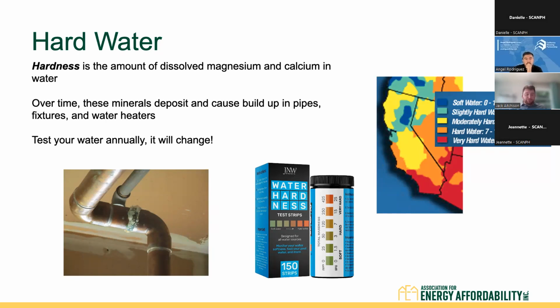In addition, this is really key: you should be testing your water annually, because municipalities will switch their water source, and how hard that water is will change. If we're in a drought, oftentimes the hardness of water just in general gets worse. But in addition, your municipality may switch over to a different water source that could be very, very hard water without notifying you. So you should be testing annually. They make pretty inexpensive test strips that are really easy to use, very self-explanatory. It takes only a few minutes, and your maintenance staff should be testing this at least once a year.